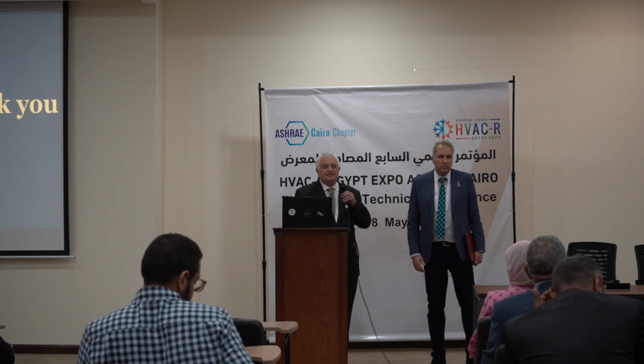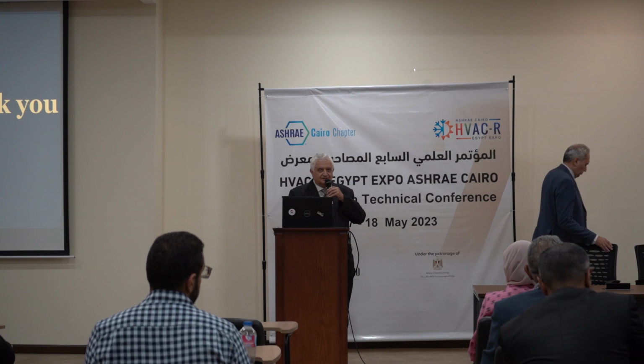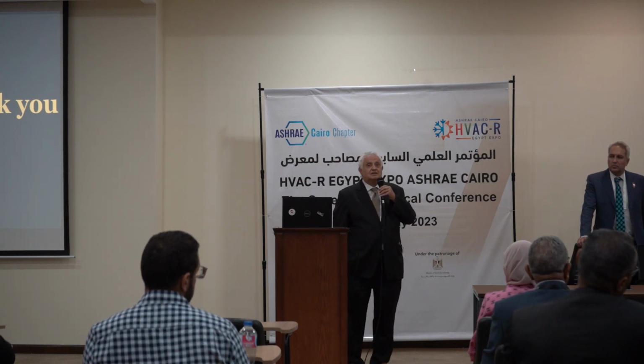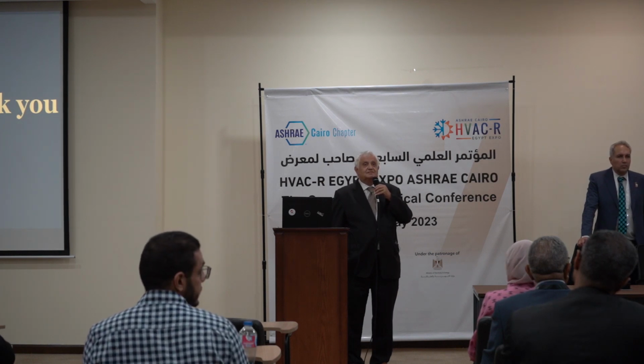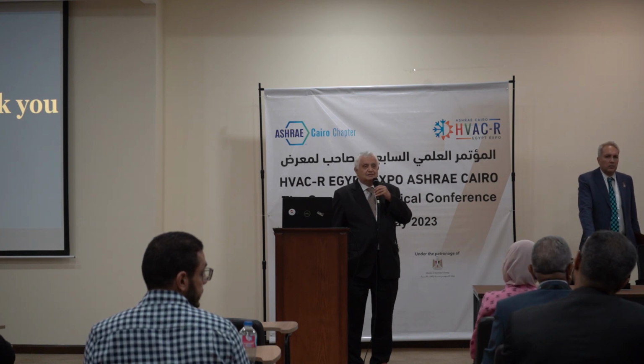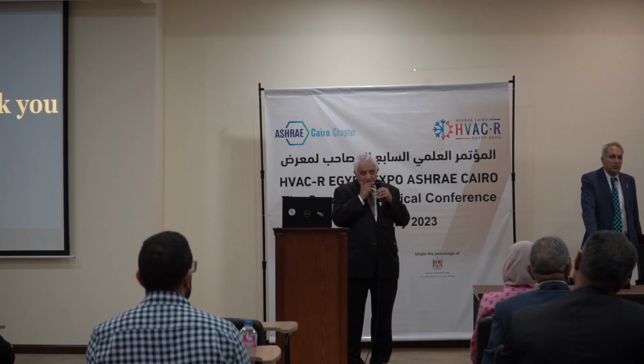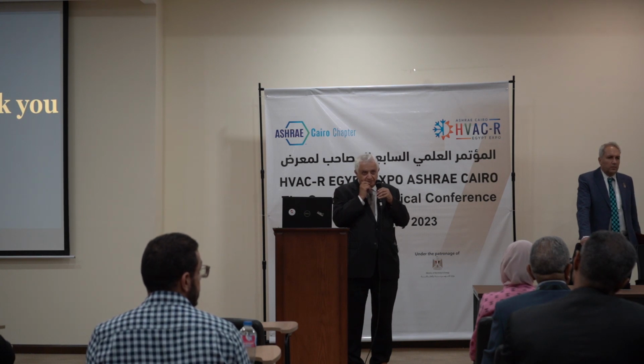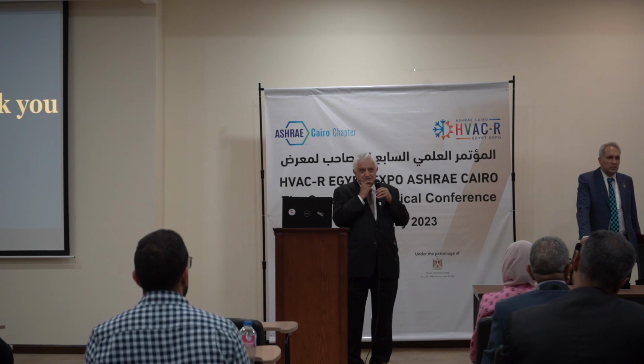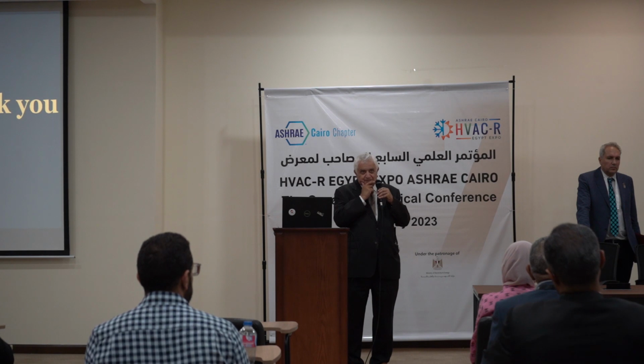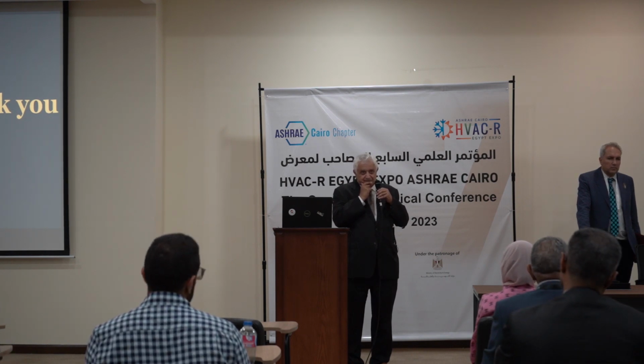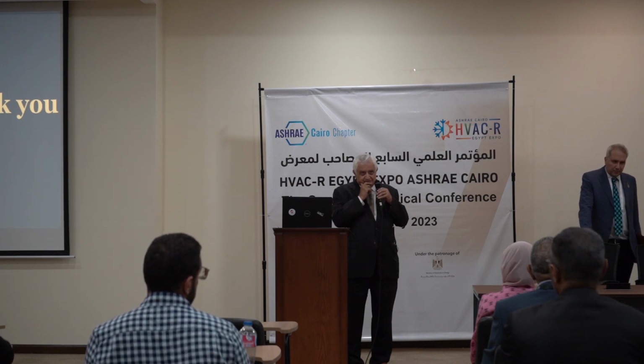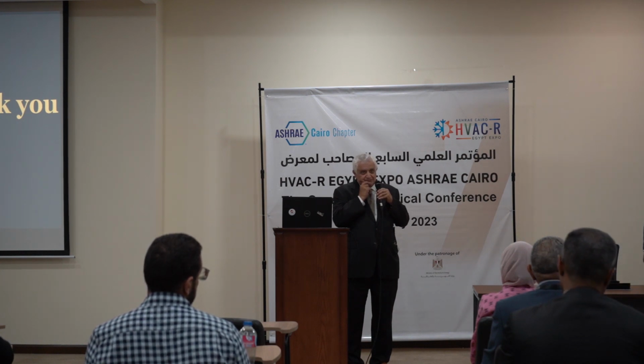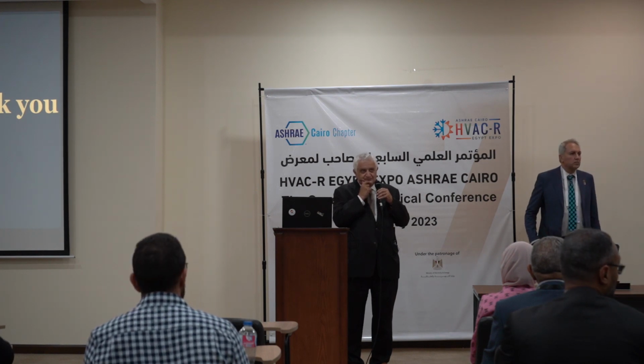As we said, this is 100% fresh air equipment, so all the results will be more efficient when you go to a hotter climate. Indeed, when you go to a hotter climate, the DX or pure DX will consume more electricity because of the high ambient temperature, while the evaporator will be very efficient in those zones. So the gap between the normal DX and the evaporator becomes very big, and at that point the two-stage hybrid evaporator is a must. There will be no comparison. If you compare in zone 2, and sometimes zone 5 which is not so hot and a bit humid, the comparison still favors the evaporator. But if you go to the hotter zones, there will be no comparison at all.